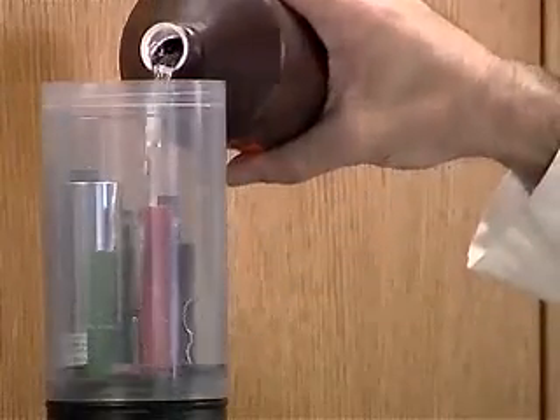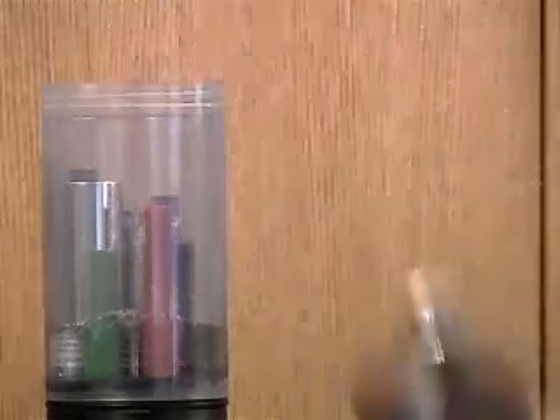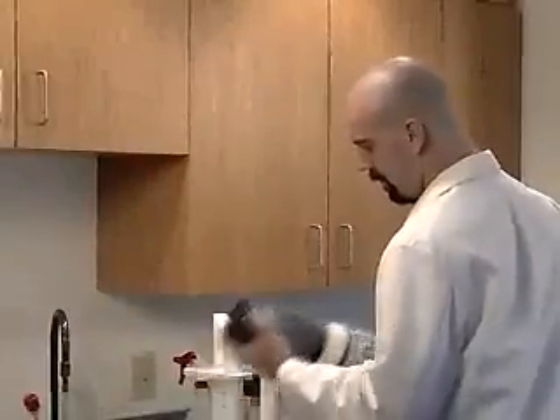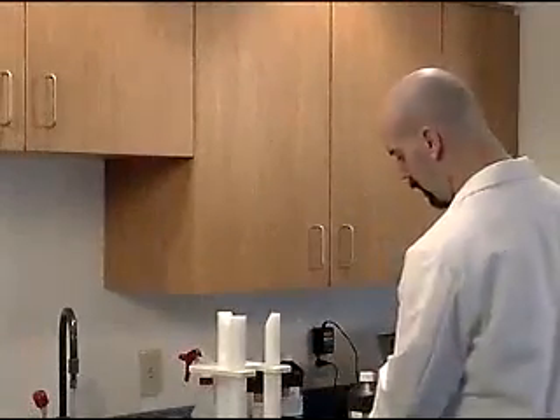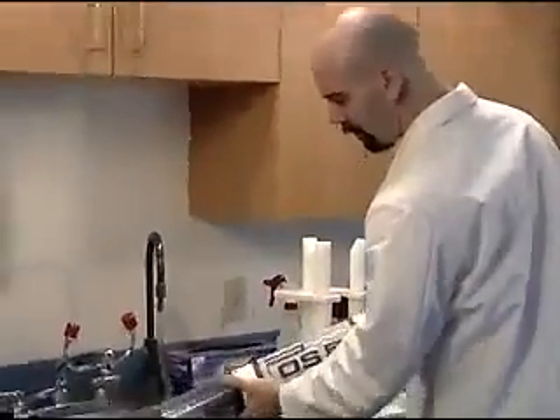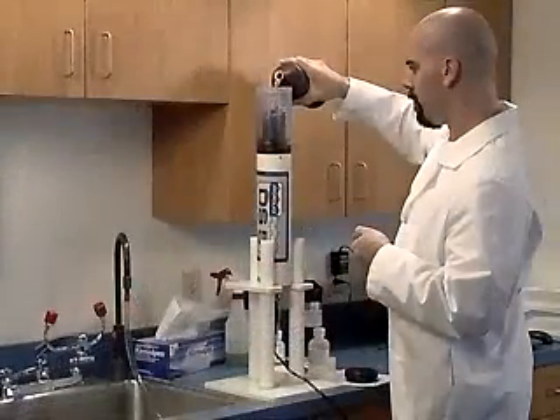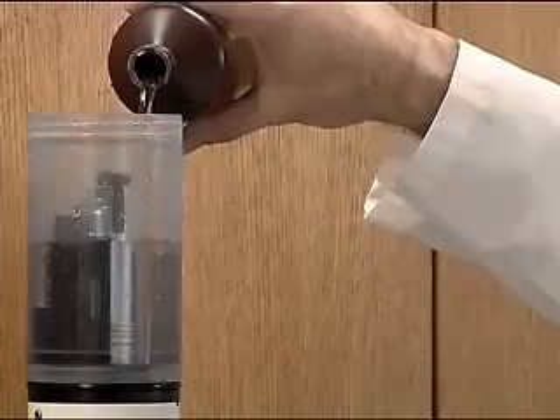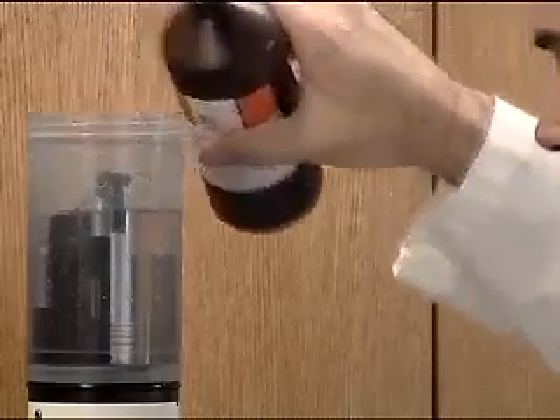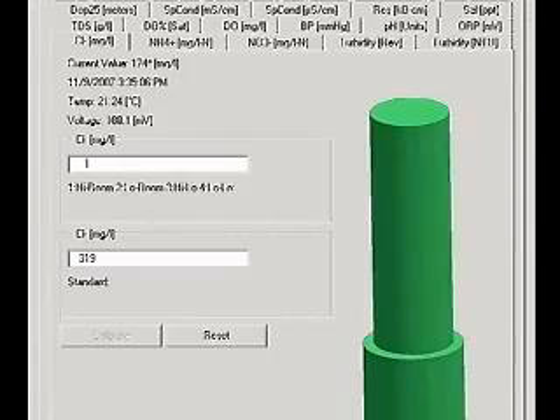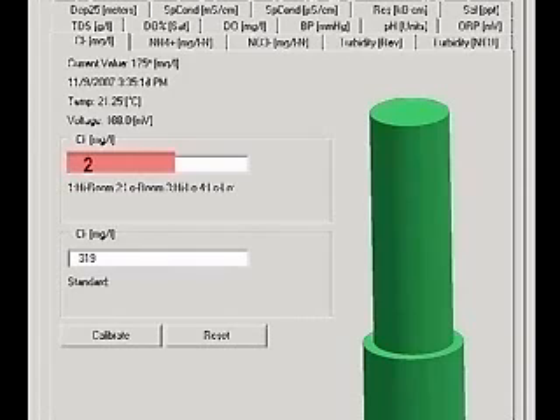Fill the cup about 25% with the room temperature low standard and screw the storage cap on. Shake for 6 seconds. Remove the storage cap and pour the standard out. Fill the cup with room temperature low standard again, this time covering the ion tip and the pH sensor. Wait 5 minutes for the readings to stabilize. When the readings are stable, type a value of 2 in the first box to designate the low standard.